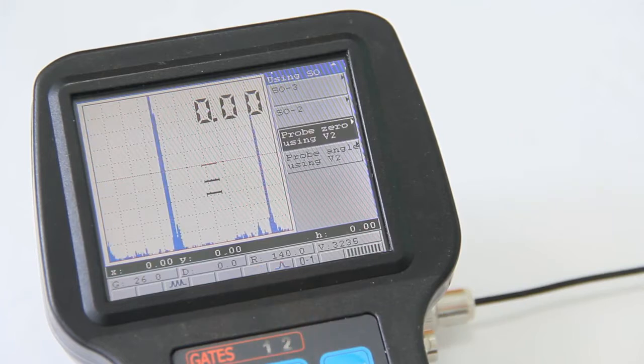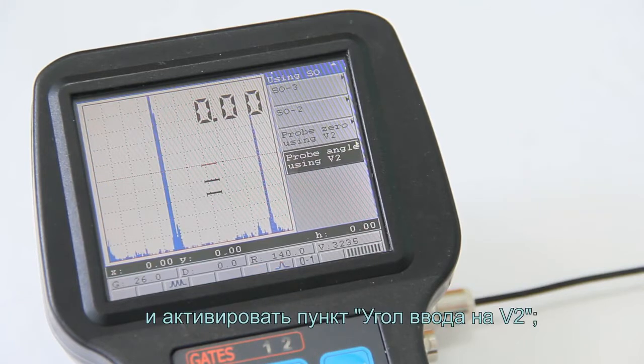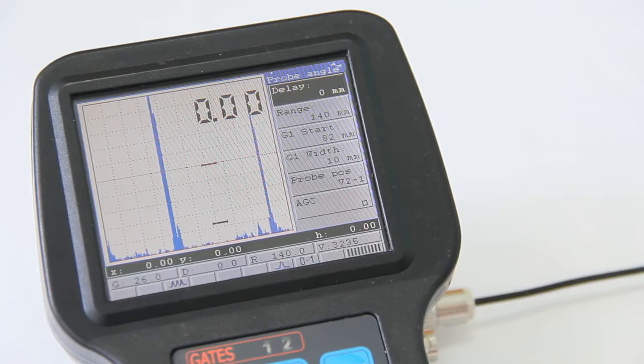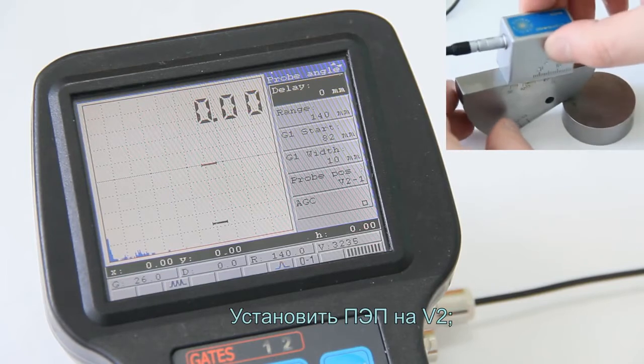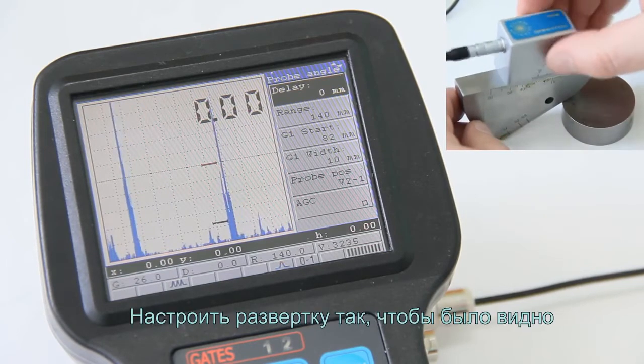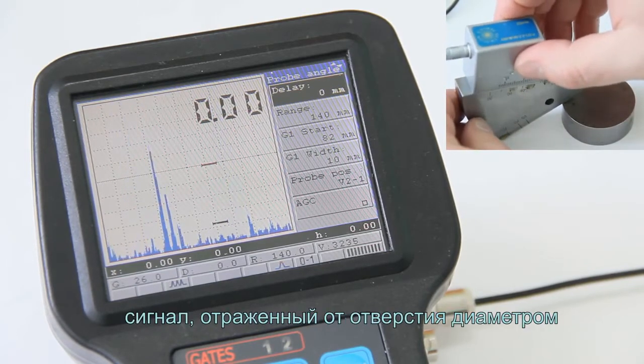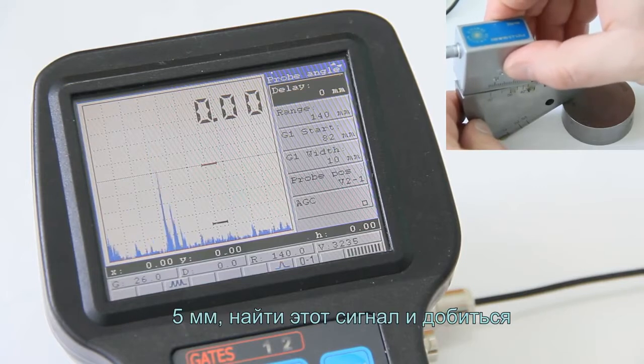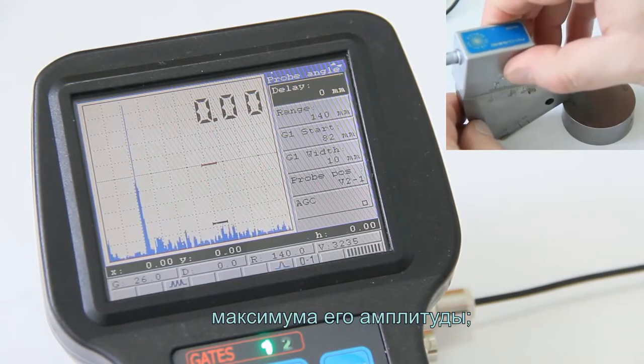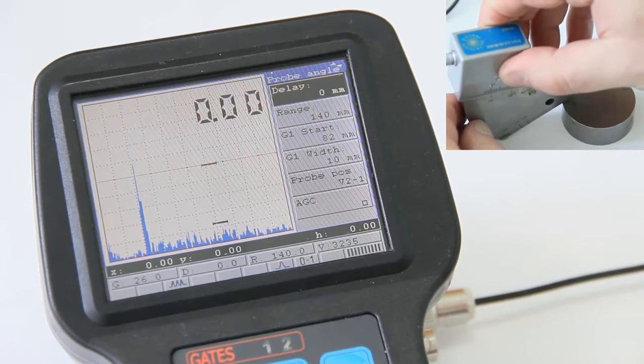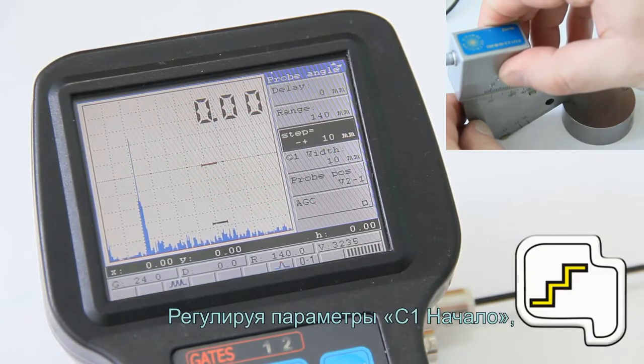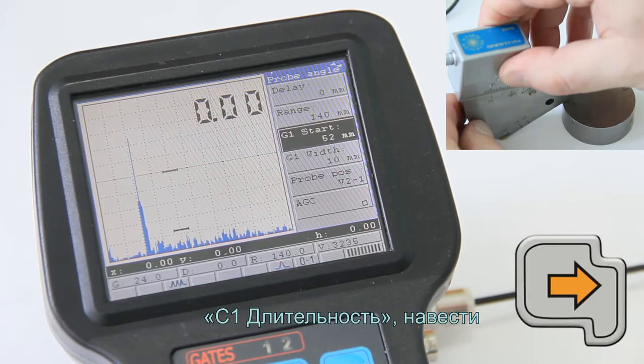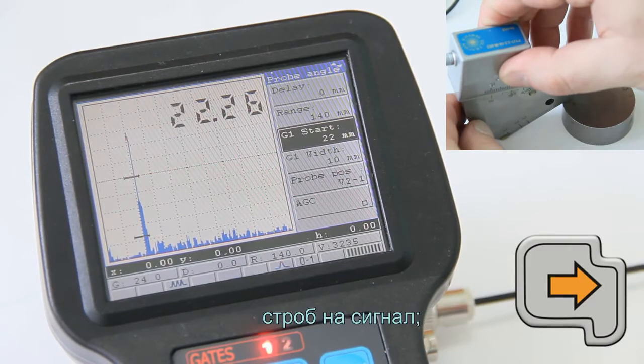Return to sub-menu using SO and activate item Probe Angle using V2. Place the probe at V2 block. Adjust the sweep in such a way to see the signal reflected from 5 mm diameter hole, then find this signal and achieve its maximum amplitude. By adjusting the G1 start and G1 width parameters, gauge the signal.